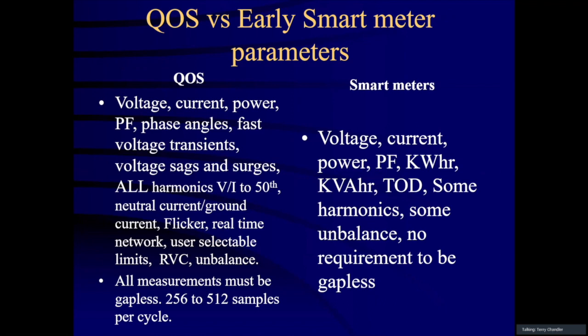Just a little review of the parameters for quality of supply. So they've got voltage, current, power. These are parameters measured by the utilities, typically in the substation, at a substation bus, or sometimes the substation feeders. So voltage, current, power, power factor, phase angles, fast voltage transients, voltage sags and surges, all harmonics, which today the typical is the 50th, although most instruments today can measure up to the 125th or higher. Neutral current. Ground current, not so much for the consumer side, because they don't provide ground to the consumers, but for their internal workings in the substation, they monitor ground for a fault, which returns through ground, so they can measure that current and detect exactly when it happened. Flicker, again, real-time network, user selectable limits.